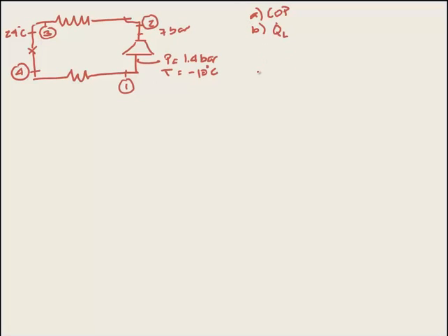So we are asked to get COP and the heat load this system can take. First of all, let's recognize that we have a mass flow rate of 6 kilograms per minute, and we can convert to kilograms per second. One minute is 60 seconds, so that is 0.1 kilograms per second of refrigerant.